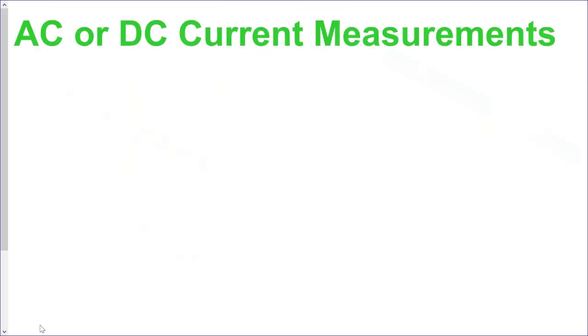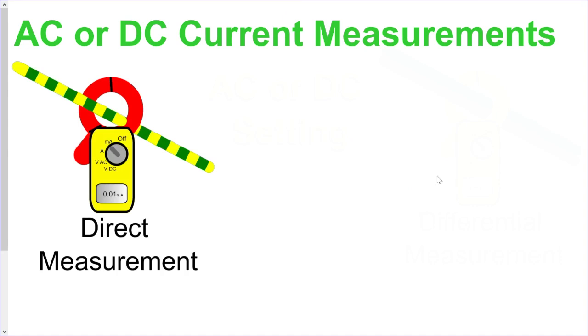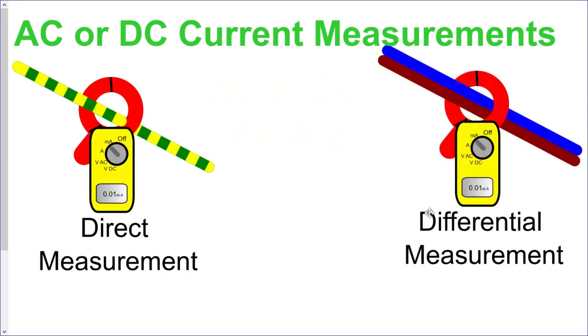when we're carrying out these measurements, there's two ways in which we can carry out these current measurements. It's either direct measurement, where we're clamping the cable and measuring directly the magnetic field on the cable for the current that's flowing through it, or we use that differential measurement where we are looking at the imbalance between the two magnetic fields as the current's flowing forwards and backwards around these cables. Yeah, if there's any current flowing down to earth, then the current clamp would be able to detect that and the difference in the two magnetic fields.